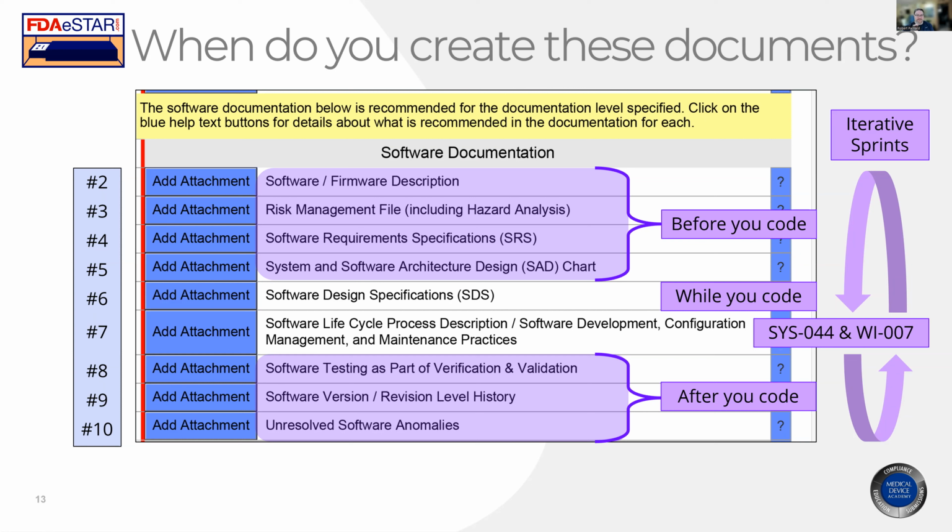And I'm going to say this multiple times, at least I'm going to try to. One of your requirements has to be software cybersecurity controls. If you don't have security controls, and the FDA lists 8 of them in the eSTAR, if you don't have those as inputs in your SRS, you're going to have a problem. You're going to have to rewrite code. You will not get it through the FDA. Why? Because now the eSTAR says where are these found in your documentation, and it should be your SRS. If it's not there, you don't have it.